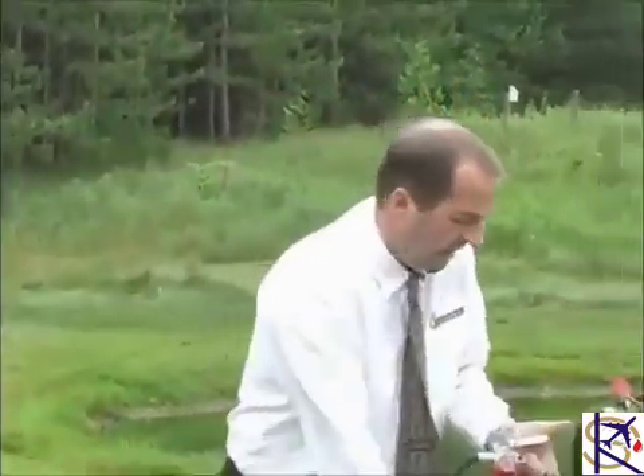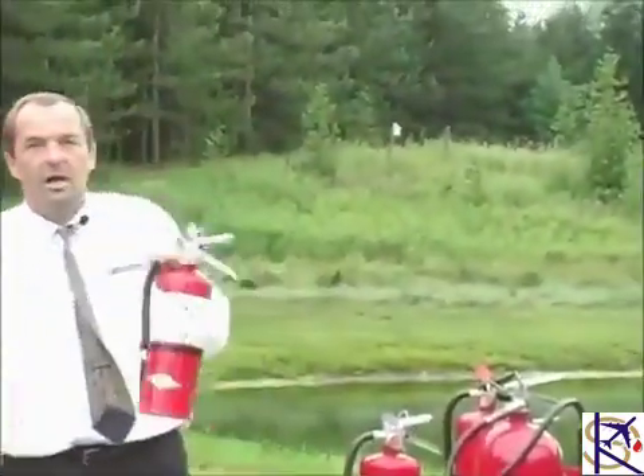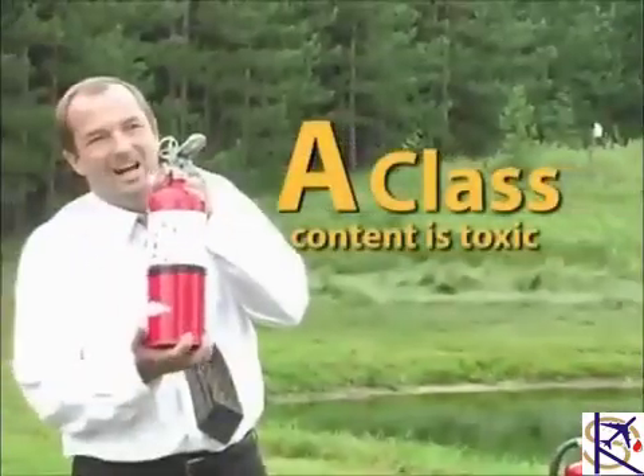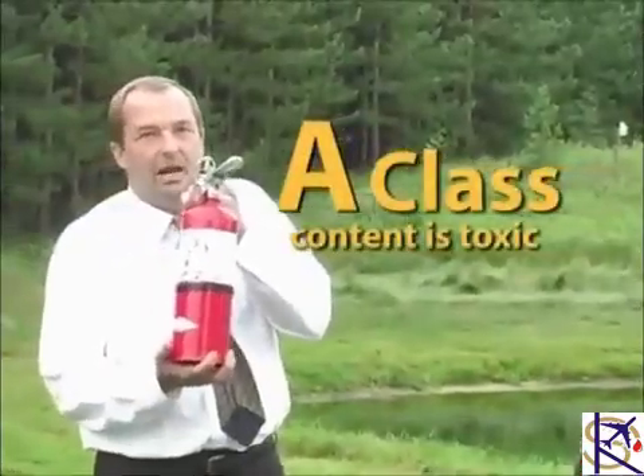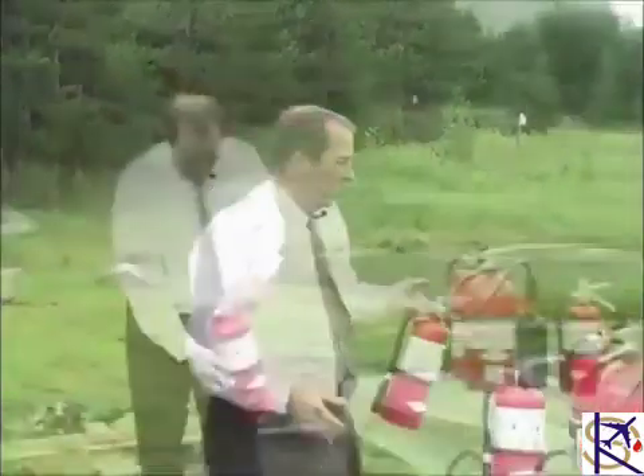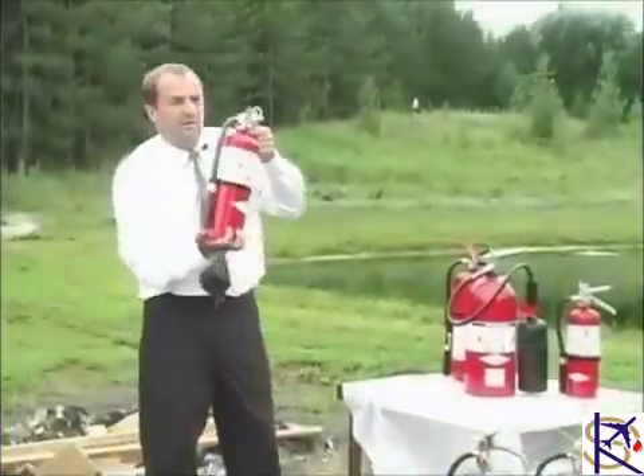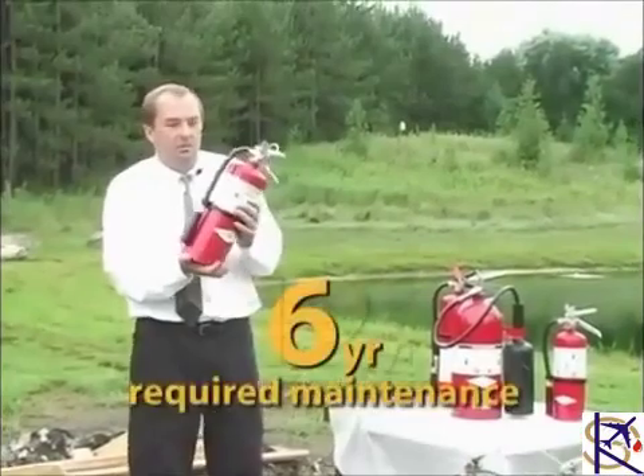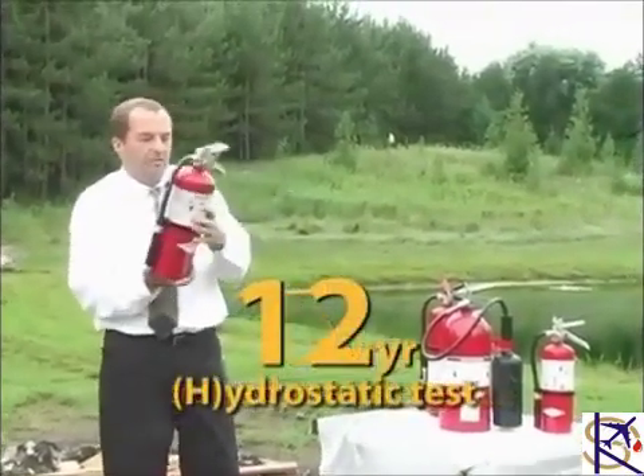An ABC would not be used in the kitchen area because of the toxicity of the A class, the A rating, which is toxic. Again, this particular one needs 6-year maintenance and a 12-year hydrostatic test from the day it was manufactured, the date on the cylinder.